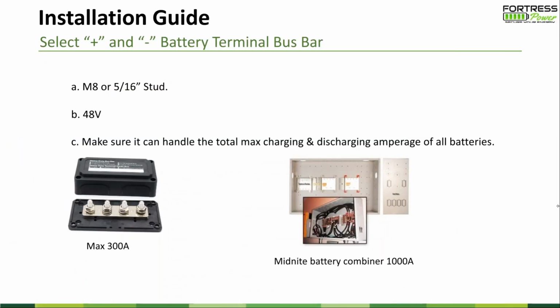Okay, next slide, please. Terminal ring and terminal bus bar selection. So we have terminal bus bars in the market. You can always choose, but be careful with it. Just want to choose the right size, so M8 or 5/16 to start. And make sure the voltage rating is fulfilled for 48 volt. Some of the bus bars are only 12 volt, but most of the bus bars have a good range of voltage.